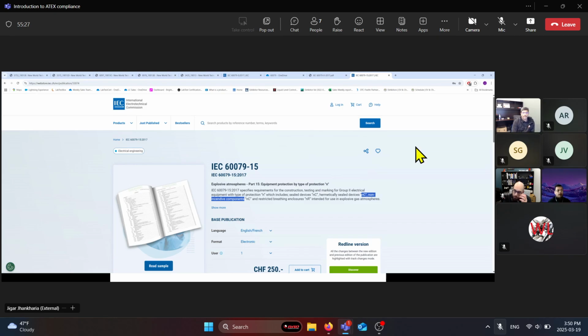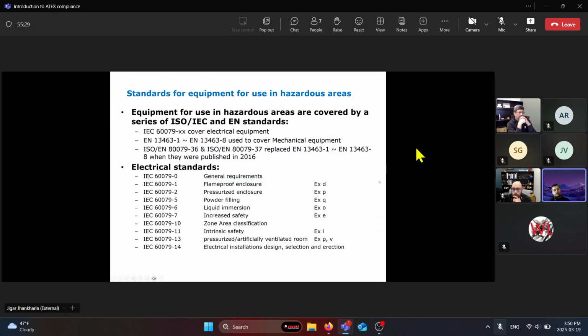So if it was in the past, then we would be looking at the -15 standard for your product, which would have been very similar to the non-incendive. But as you can see, they've changed the name, but pretty much everything in the standard is very similar to the non-incendive electrical equipment standard for CSA and UL. The -10 is for zone area classification.